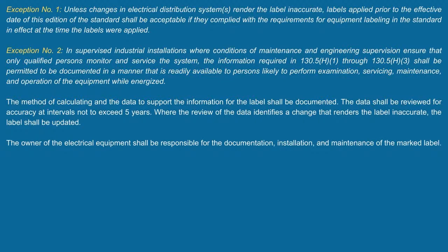The qualified person that is going to perform the examination, service, and maintenance of the equipment. All right. Now, they drop down right after that, and this is what they tell you. The method of calculating and the data to support the information for the label shall be documented. The data shall be reviewed for accuracy at intervals not to exceed 5 years, again, which is what I was talking about in exception 1. And then it says where the review of the data identifies a change that renders the label inaccurate, the label has to be what? Updated.